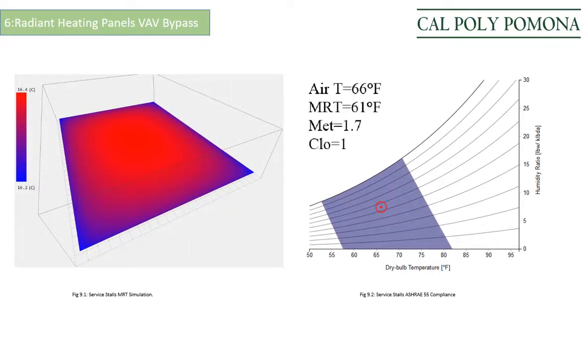According to ASHRAE 55, the major factors for a comfort zone are air temperature, mean radiant temperature, humidity, and metabolic rate of the body. Radiant floor heating provides exceptional mean radiant temperature. Since the floor has a higher surface temperature of 80 to 89 degrees Fahrenheit for this project, mean radiant temperature in sample spaces such as the service stalls and bedroom was investigated during the peak day.